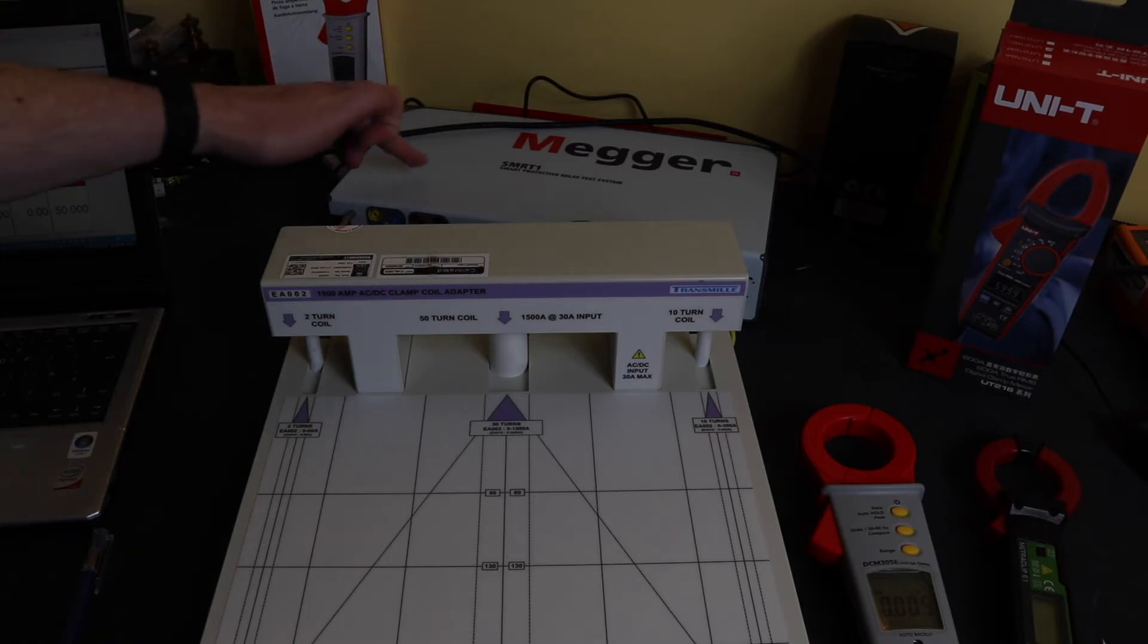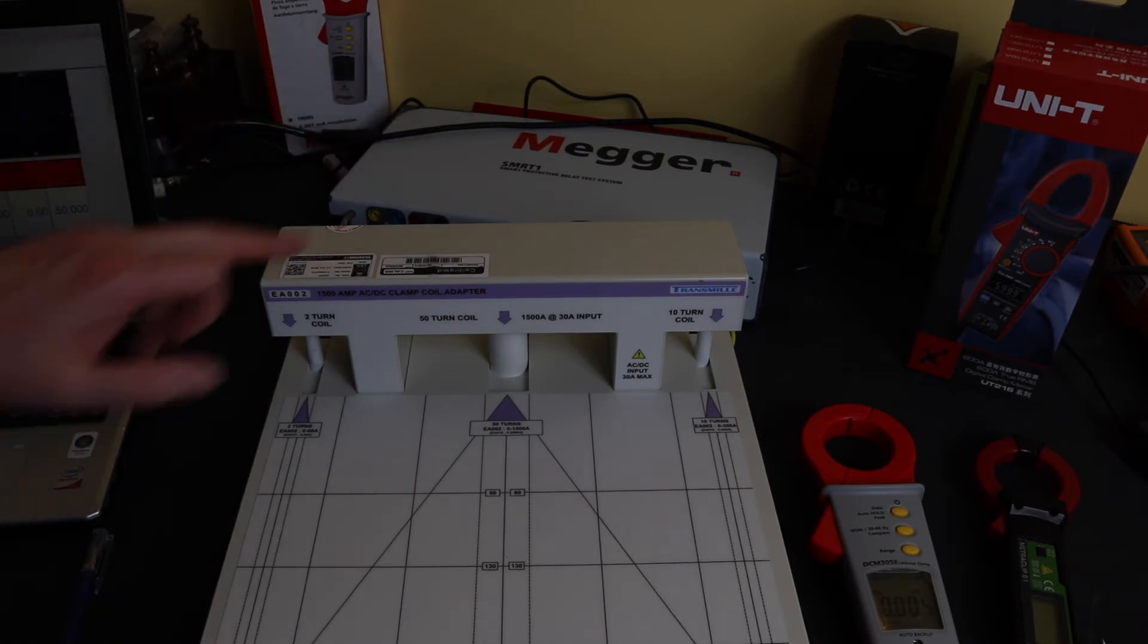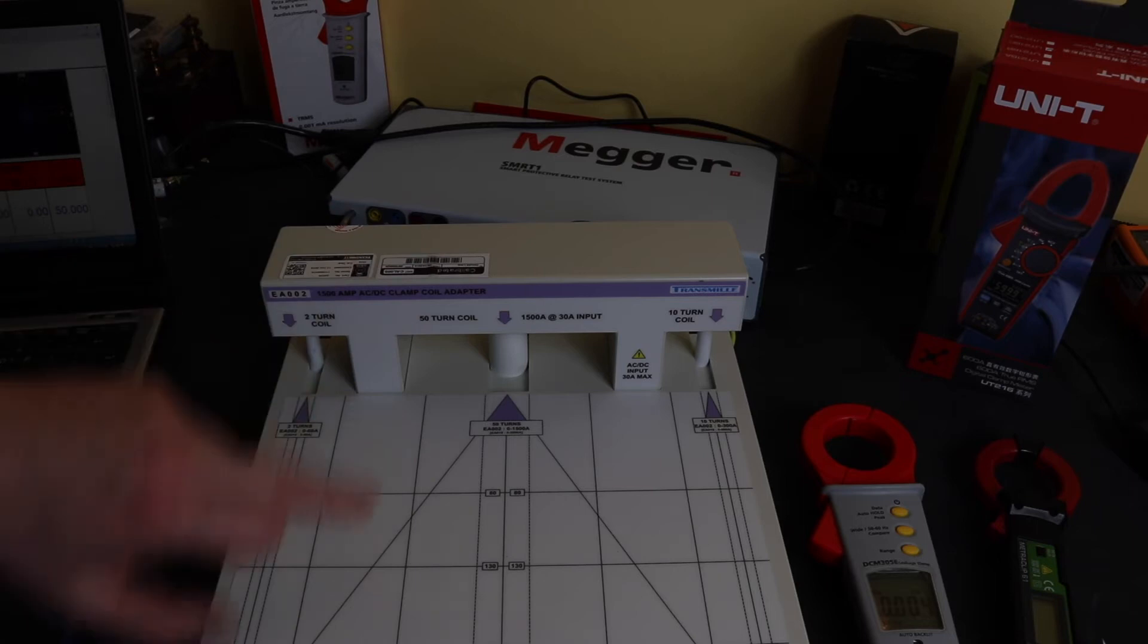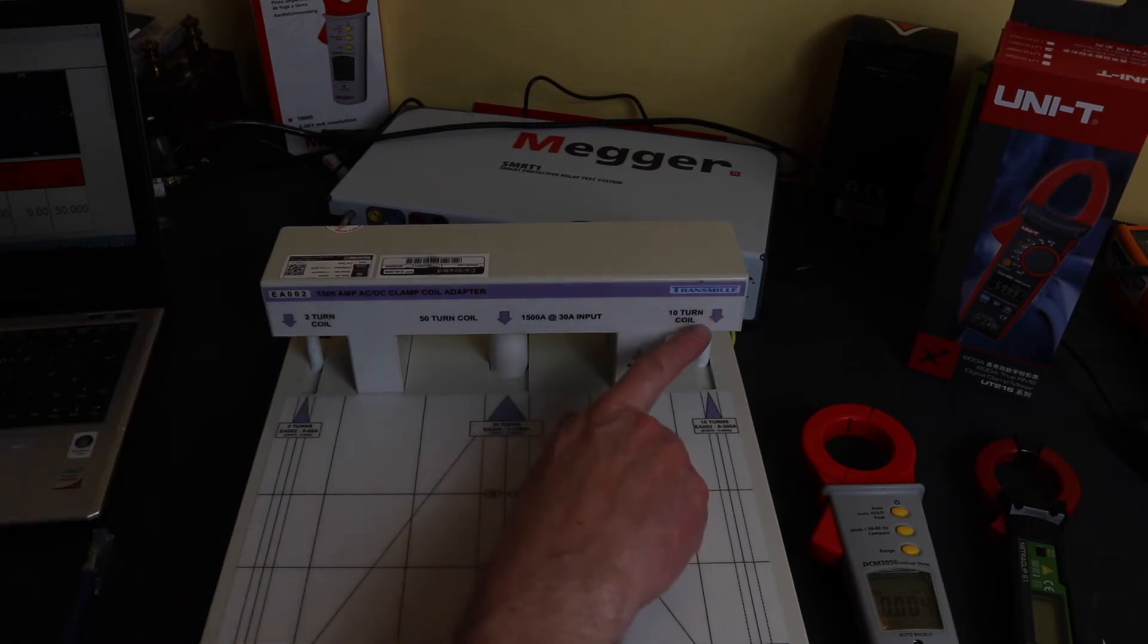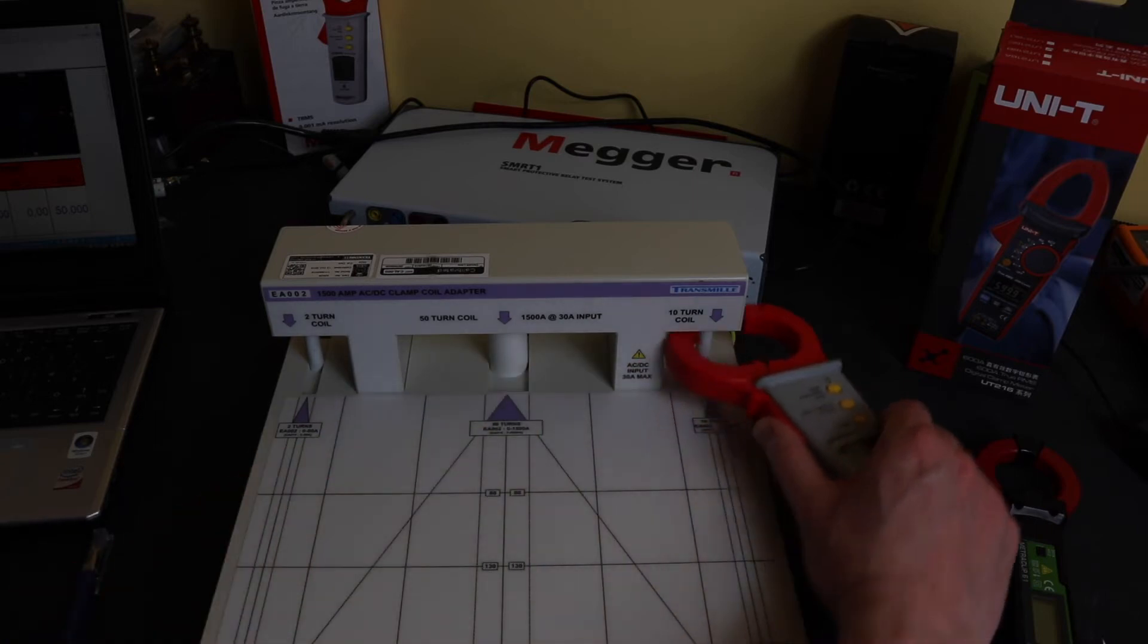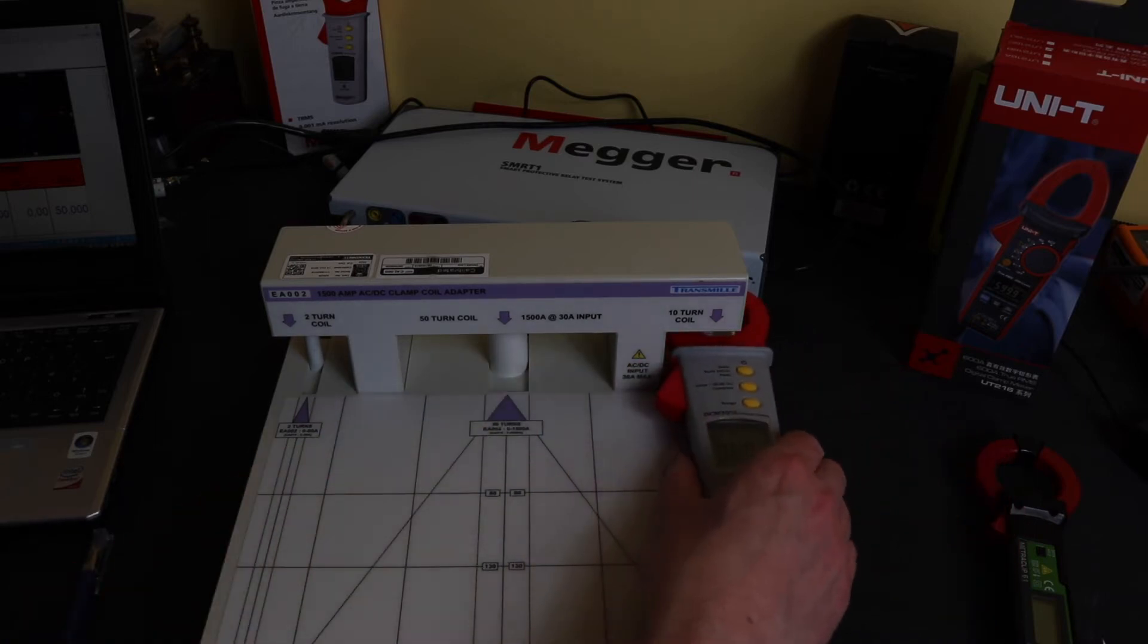So to do the tests I've got one Megger SMRT injection unit at the back there that's going to be putting current into the current clamp table you see in the front there. I'm going to be using the 10 turn coil initially so we'll take a look at Megger and set him up and I'll see if I can zoom in onto the screen a little bit better.